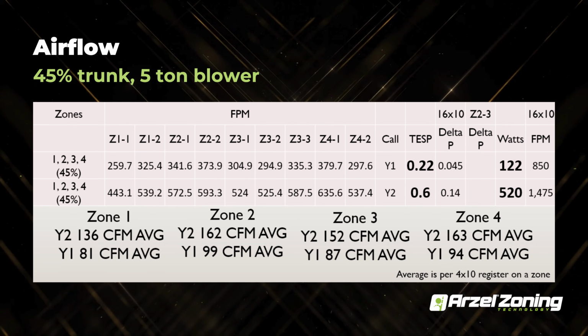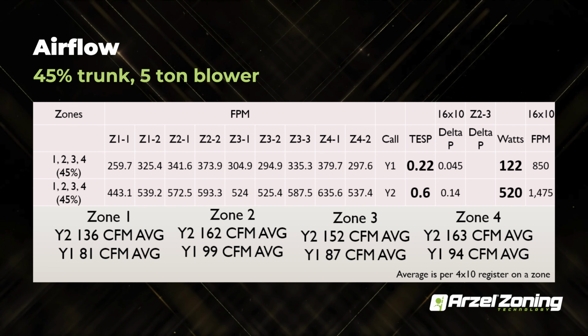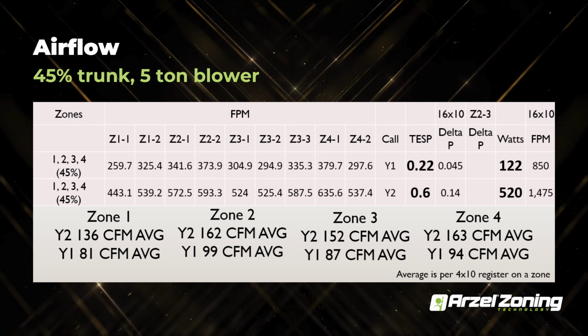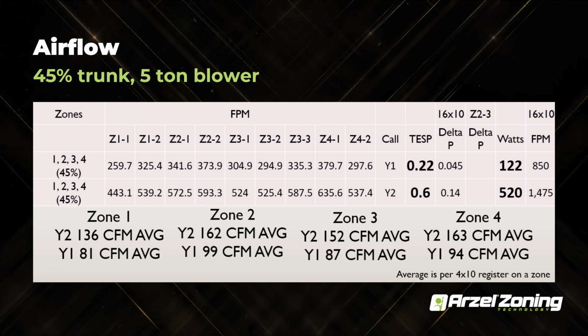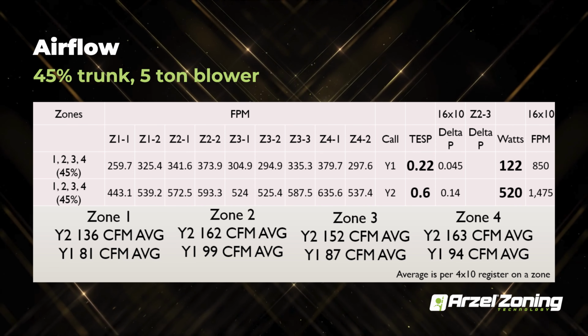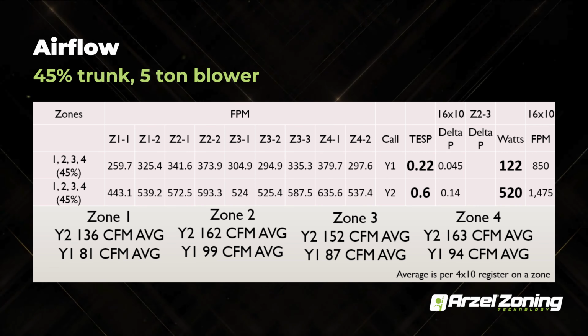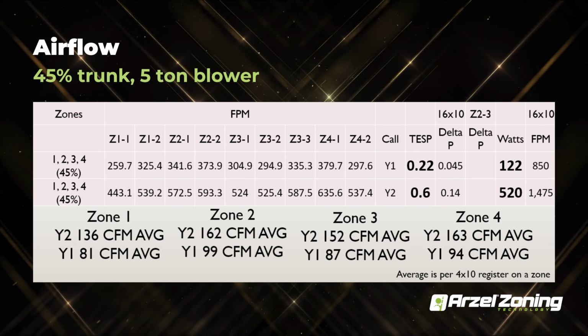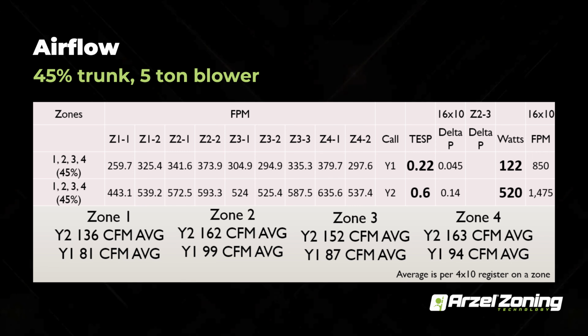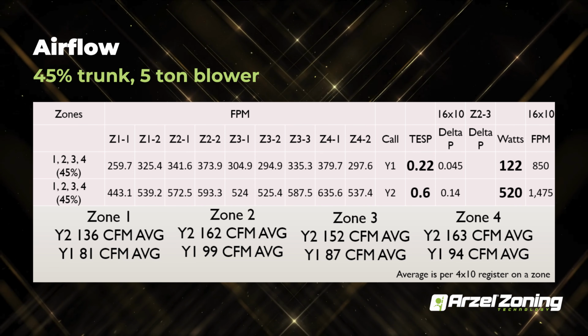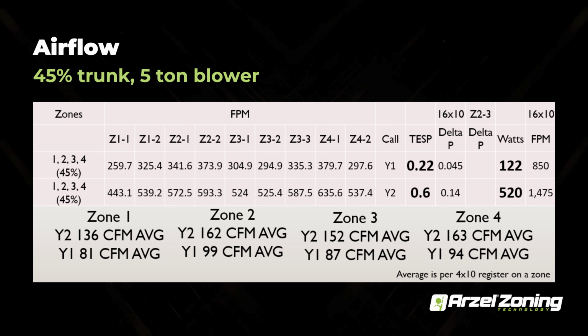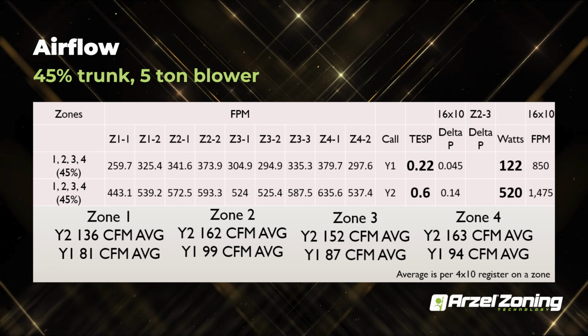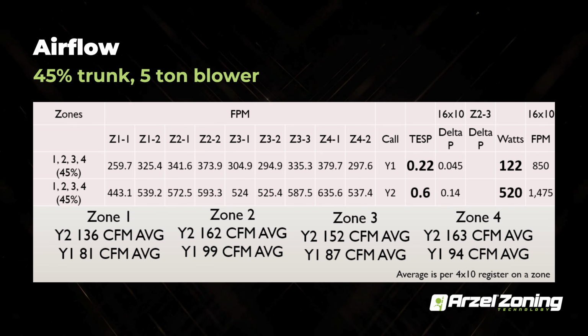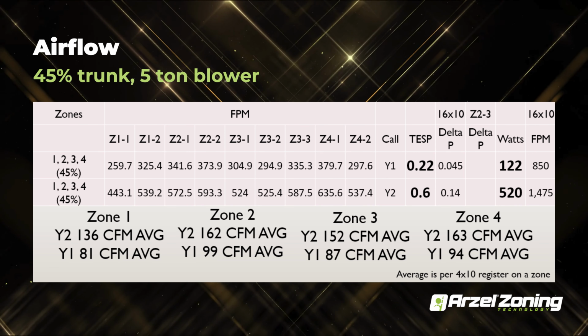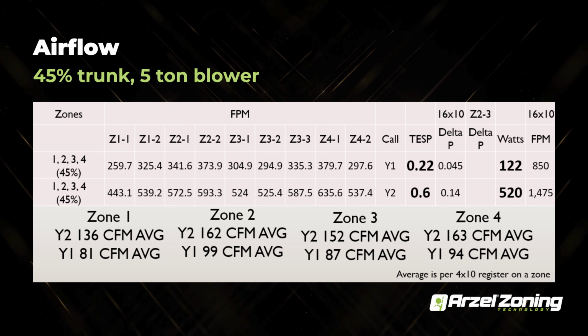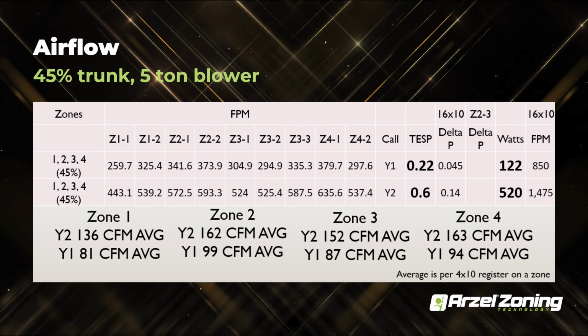So when we do start zoning it, this is going to be 45% of the trunk closed off. So we're going to close off the one zone. When we did that, our Y1 output, we got a 0.22 total external system pressure with 122 watts on our blower motor. And then our Y2 output was 0.6 total system static, and 520 watts was our blower output. So you can see that difference just between Y1 and Y2 with the zoning on, how much of a difference that static pressure is going to make, and your wattage is going to increase when you're doing that Y2 output on those zones. So this is a pretty typical 2-zone system.